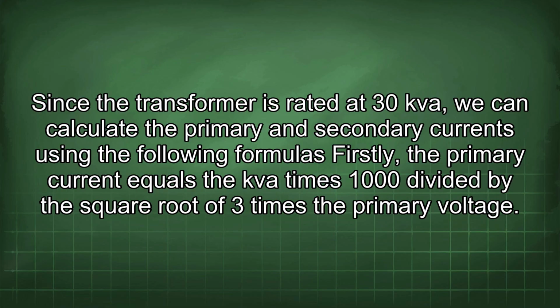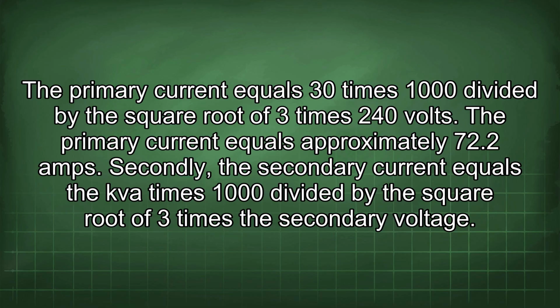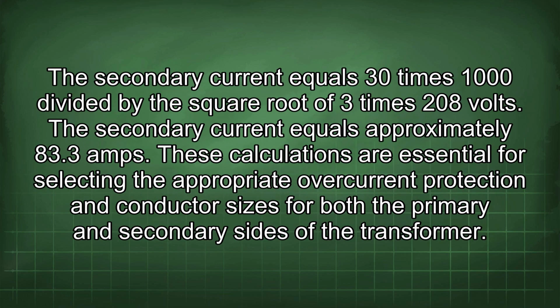Firstly, the primary current equals the kVA times 1000 divided by the square root of 3 times the primary voltage. The primary current equals 30 times 1000 divided by the square root of 3 times 240 volts. The primary current equals approximately 72.2 amps. Secondly, the secondary current equals the kVA times 1000 divided by the square root of 3 times the secondary voltage. The secondary current equals 30 times 1000 divided by the square root of 3 times 208 volts. The secondary current equals approximately 83.3 amps.